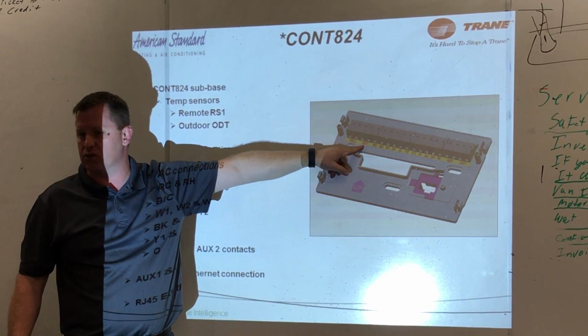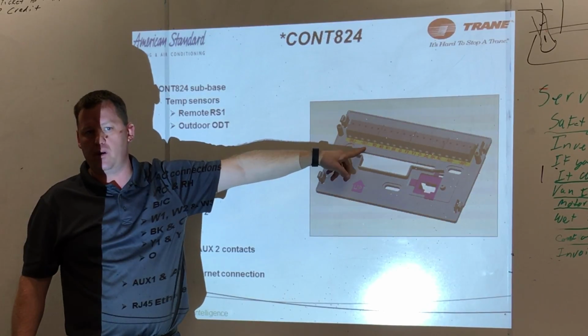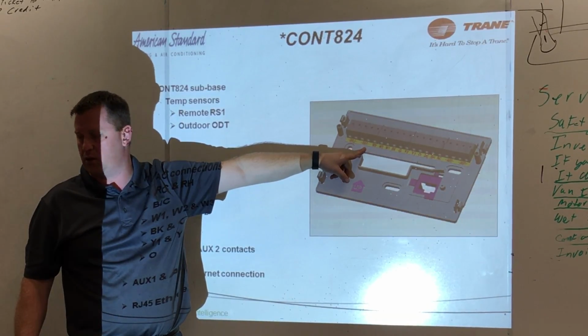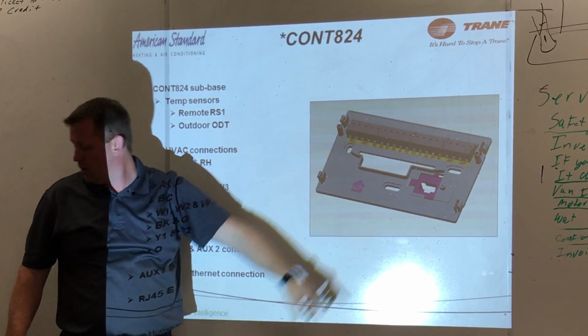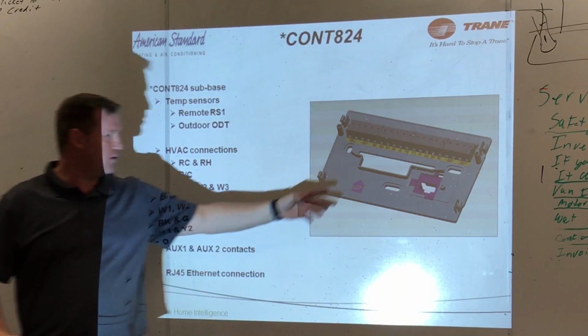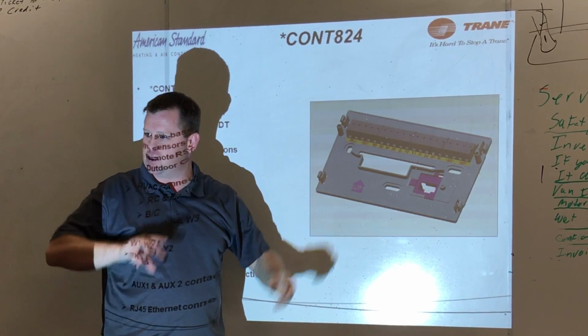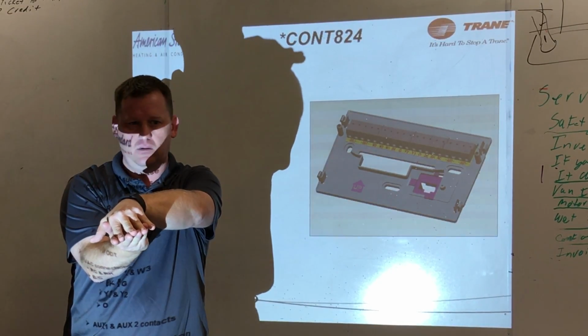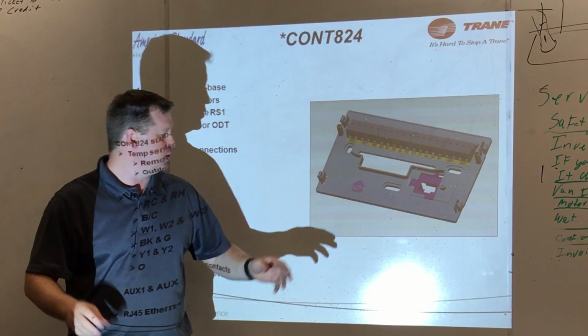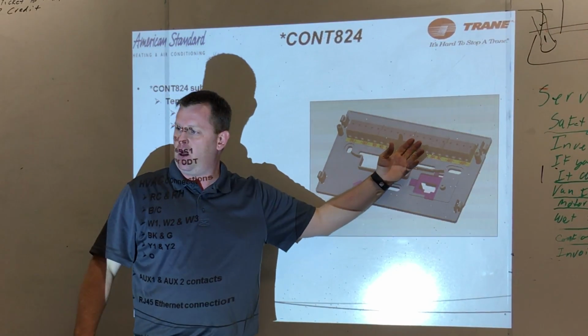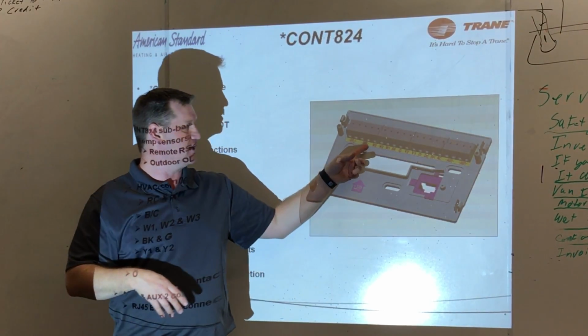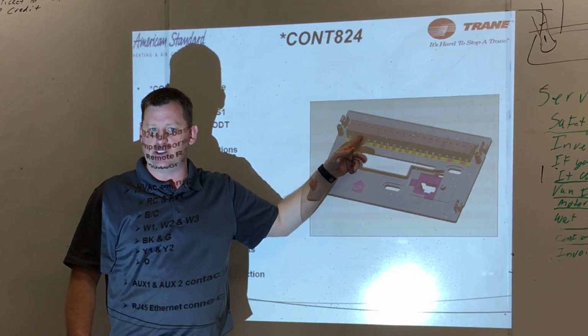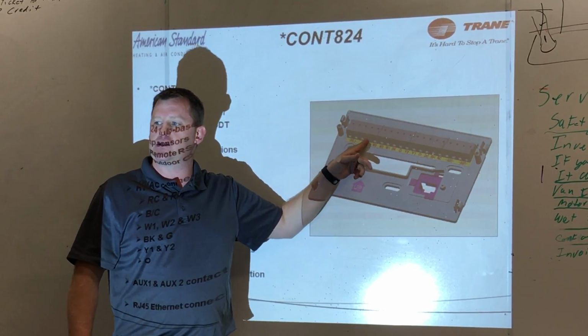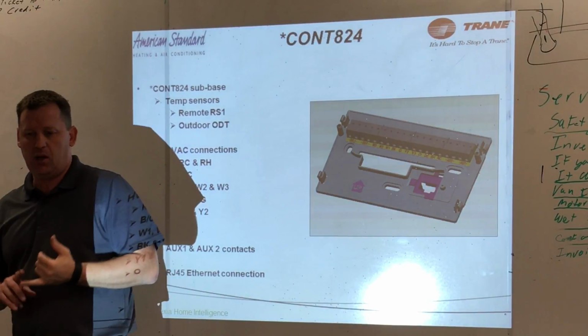Also, outdoor temperature sensors need to be in separate cables. Here's why: when we run 2 wires for the outdoor sensor in the same cable, those wires are twisted together and intermingled. What happens is when there's noise on the AC line, it gets injected into the outdoor sensor signal, which is DC, and it messes up the thermostat.